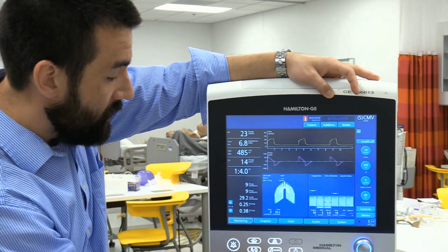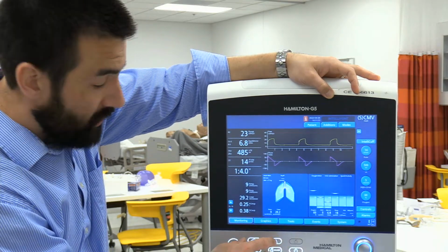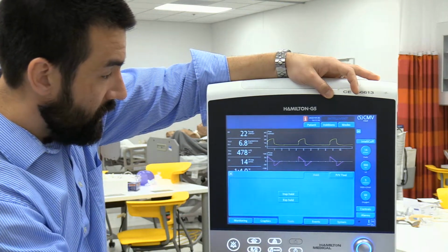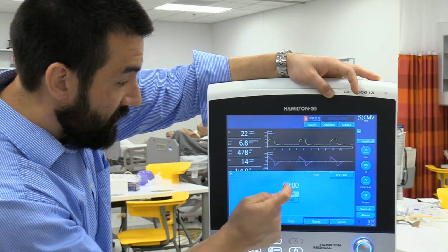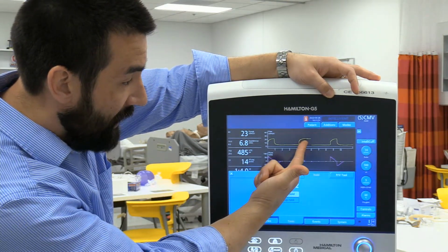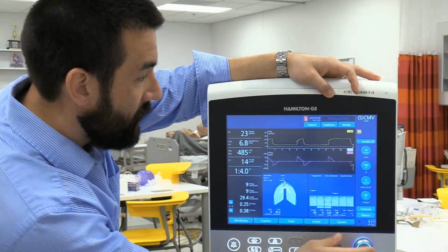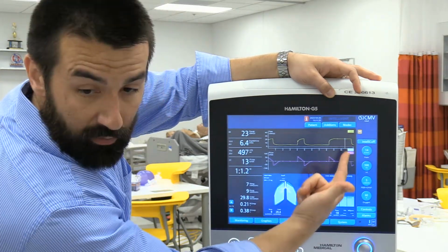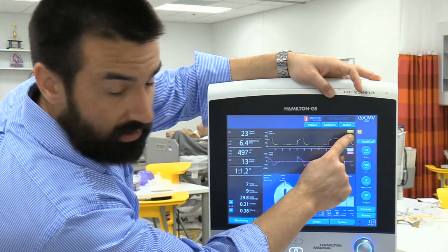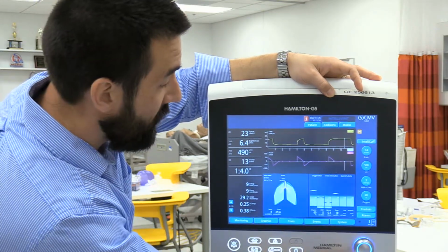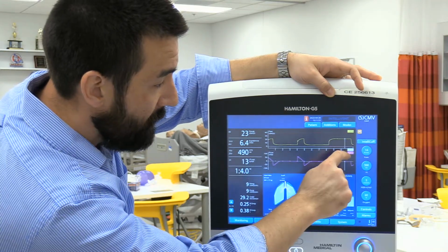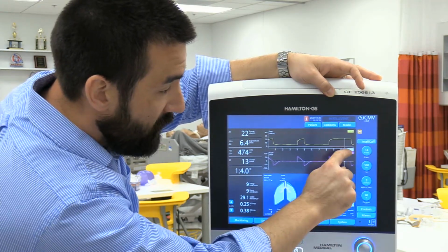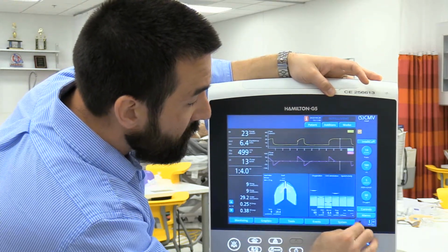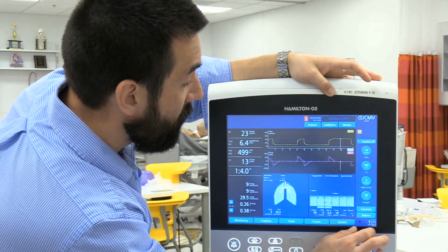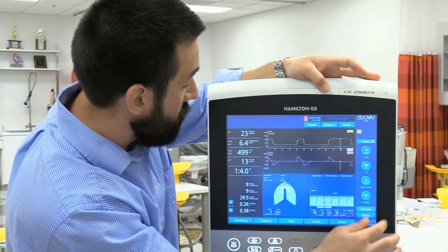So let's talk about doing a plateau on this vent. It's a little bit more involved. You're going to go to Tools. You're going to try and get it timed up where it's on the left-hand side. You're going to hit Hold. It doesn't hold until it actually gives the breath and then drops down. And you can see I have my lung set up so it freezes it. I have to use the little wheel on the Hamilton G5. It's going to show me my plateau pressure over here. On the C3s, some of them show it over here, so be careful. It also shows you time and flow. The white number is time. It shows you at what point in time you're looking. We want to find a good period with zero flow movement, allowing total equilibration between the Y and my alveoli. That would be the pressure we want to take it from.